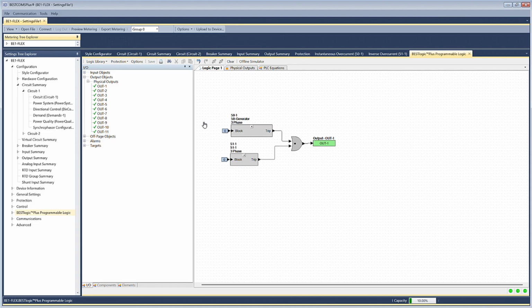In addition to the logic, what's also happened is I've turned on targets, I've turned on sequence events, had a handful of alarms turned on, the fault recorder is turned on, and again, a bunch of those things behind the scenes that it's done automatically. If I did want to do the simulator I had shown previously, I can turn it on just by clicking my offline simulator, double click a trip, watch it flow through the logic, and in this particular case, very simple logic, but I'll watch output 1 transition. So turn that off, and this is a happy and healthy settings file that I can upload to a relay.